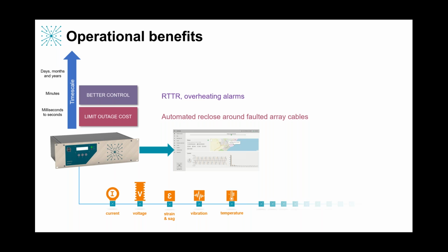But while there's not a fault and these sensors are out there recording everything that's happening, it's also very good for enhanced real-time control functions. That's in human timescales of seconds and minutes, where we're looking for things like overheating terminations and setting alarms that can warn people of a problem that's about to happen to prevent catastrophic damage before it gets too big of a problem. And also that enables real-time thermal rating, which I'll get onto in a moment.